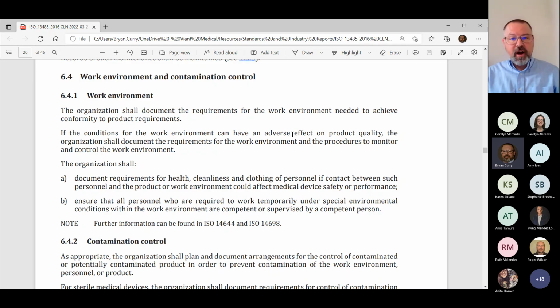The second area where the work environment can impact product conformity or product requirements is in the area of things we call foreign matter, particulates, or sometimes just particulate contamination. Most customers will have some level of specification that describes the amount of foreign material that can exist, whether it's on the device, in a packaged tray, or in a packaged pouch. And the clean room environment itself is intended, and there are things that we do in terms of the height of workbenches and the PPE that we ask personnel to wear. All of those things are intended to have a positive impact on the amount of particulates or foreign material that are circulating in the room on an ongoing basis, and their ability to potentially be introduced to the product, right?